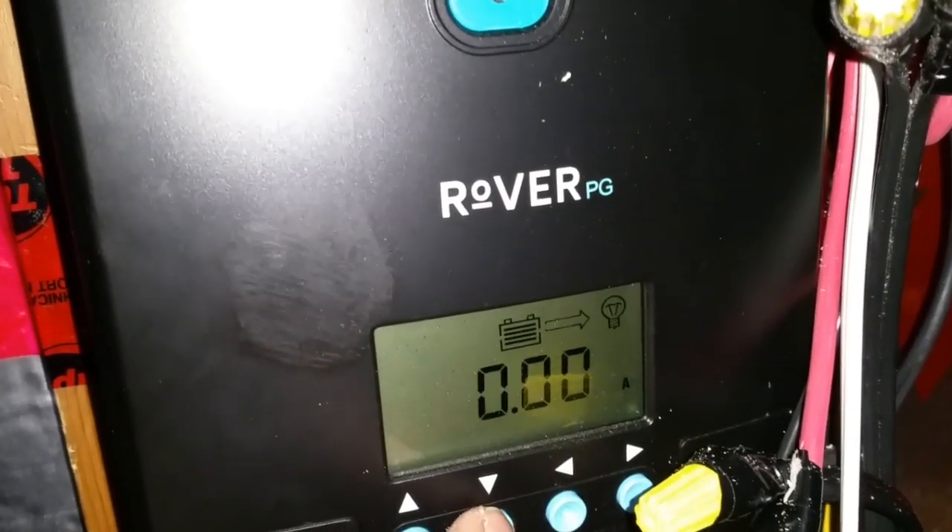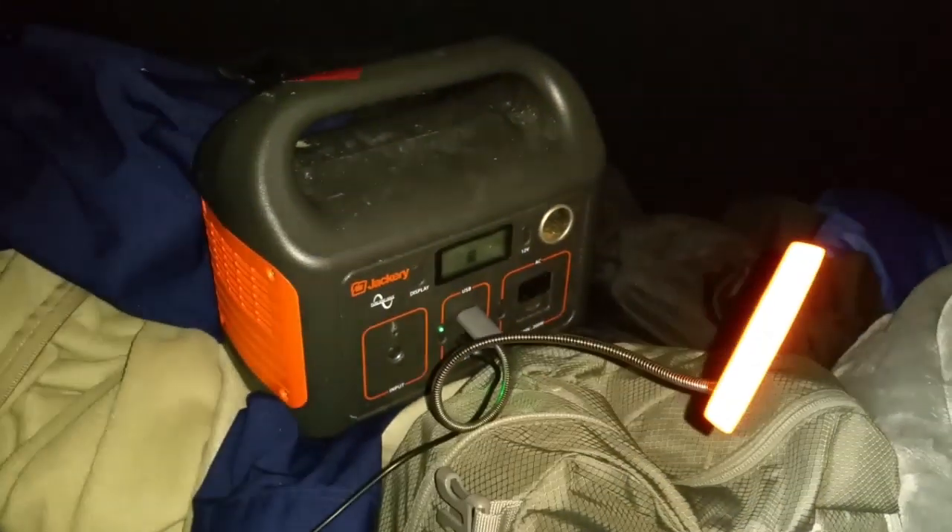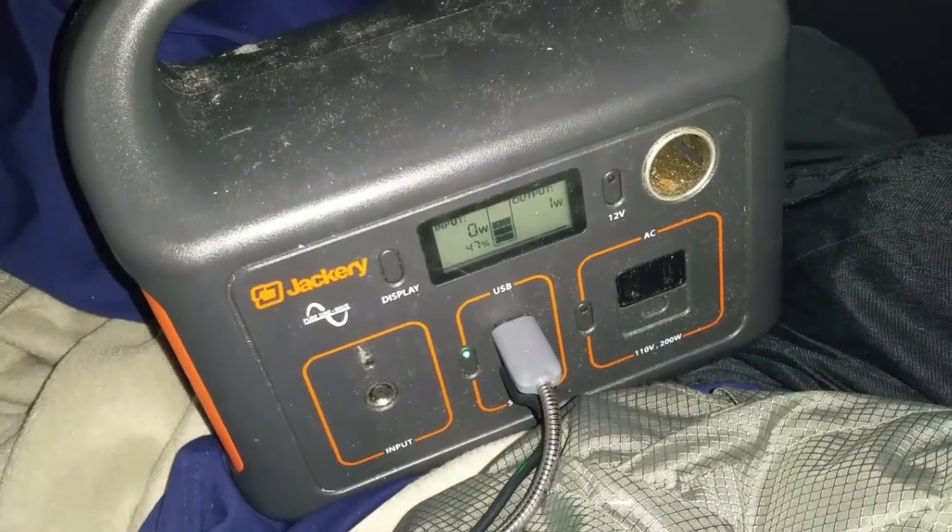With the solenoid, you're just getting juice pumped into that sucker — the house batteries are getting juiced big time. So if you're going on a five-hour trip and the whole time your batteries are just getting full of amps, will they not get overloaded? It's just an alternator directly connected to your startup battery, which is directly connected to your house battery, with a little solenoid in between. There's no computer interface, nothing regulating the power going into that house battery, which may mean that you will shorten the life of your batteries.